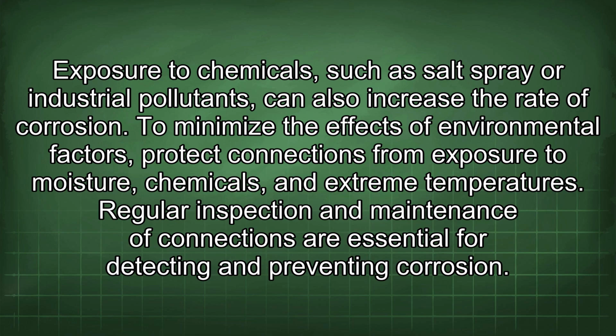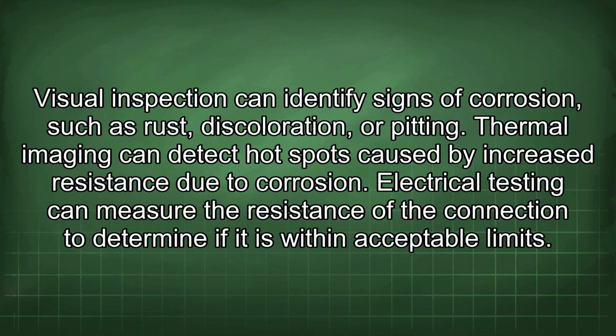Regular inspection and maintenance of connections are essential for detecting and preventing corrosion. Visual inspection can identify signs of corrosion, such as rust, discoloration, or pitting. Thermal imaging can detect hot spots caused by increased resistance due to corrosion. Electrical testing can measure the resistance of the connection to determine if it is within acceptable limits.